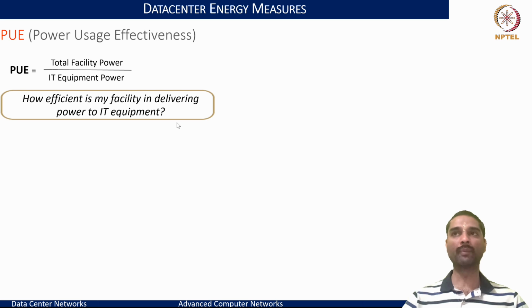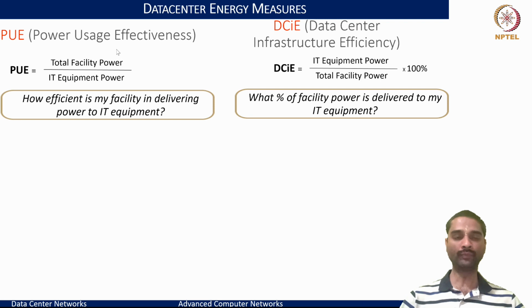PUE is the measure of energy efficiency of a data center. The IT equipment part of the power is the core component, taken as a subset of the total power fed in, channeled partly for IT equipment and partly for other aspects. In a nutshell, PUE measures the efficiency of the data center facility in delivering power to the IT equipment. The reciprocal, 1 over PUE, gives the percentage of total data center power delivered to the IT equipment - that's the DCiE, which equals 1 over PUE multiplied by 100. Both metrics guide how power is being utilized for the data center.